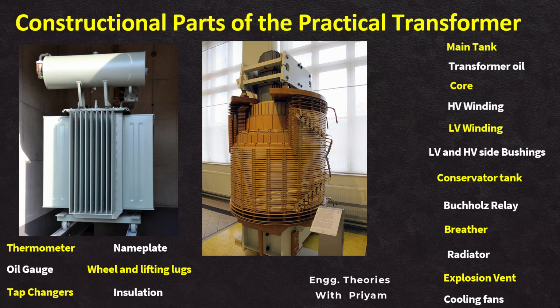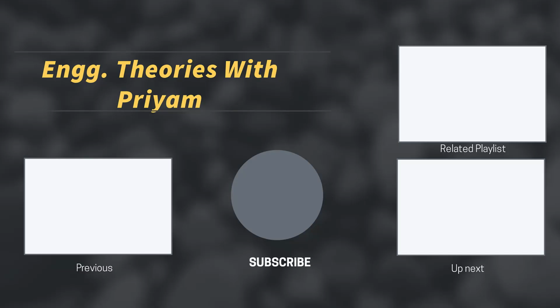There are a lot of monitoring devices inside the transformer. We have already talked about the thermometer and oil level gauge. There are also the pressure relief device, winding temperature indicator, oil temperature indicator, pressure and vacuum gauge, and also the tap position indicator and moisture meter. These devices are included in the transformer in order to check different levels of temperature, moisture, and pressure inside the transformer. This concludes our discussion for this lecture.